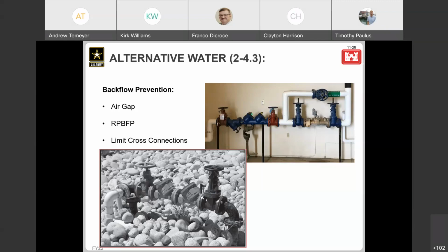So the photo in gray - if you look at the left of the photo, this is a potable water connection to a non-potable source. Their cross-contamination plan is that they would actually have to physically unbolt the elbow and turn it to be able to connect up to the other source. So it won't physically fit a T. That way you don't have someone that just accidentally opens a valve and cross-contaminates.